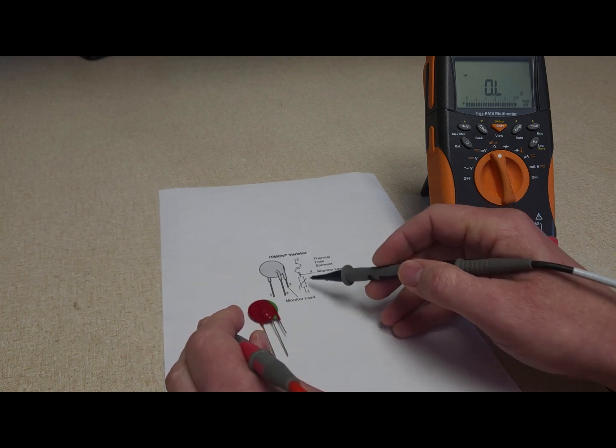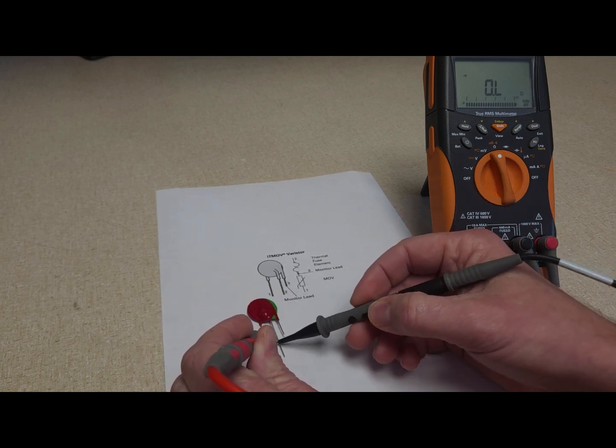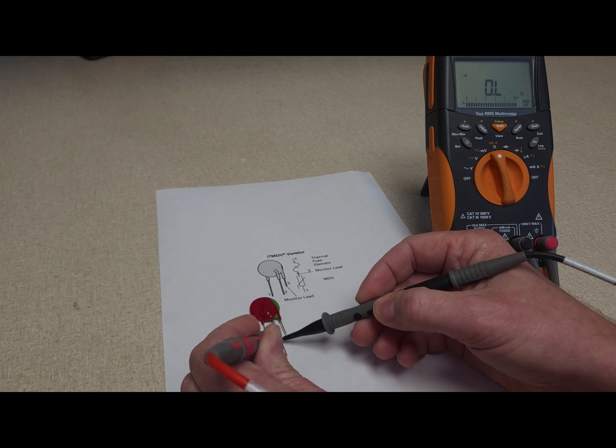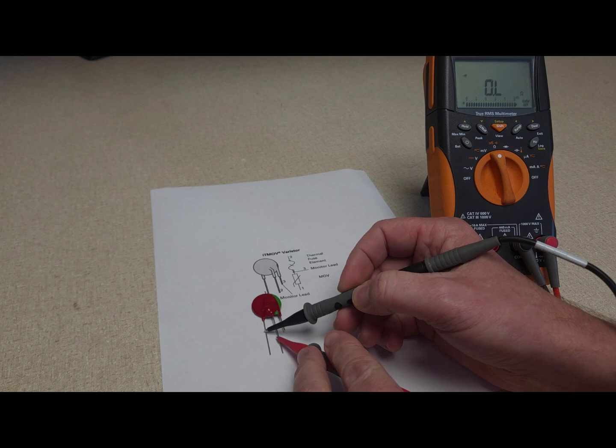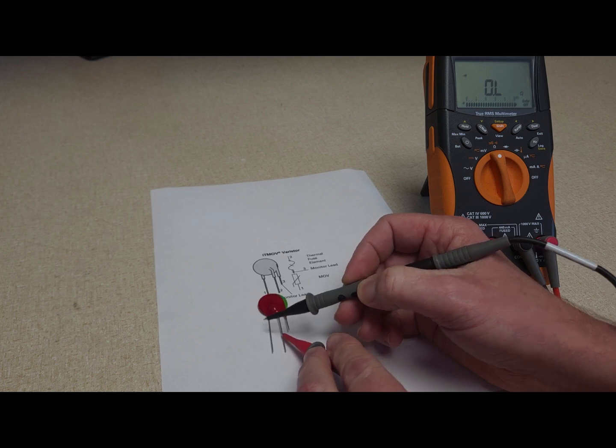To test across the MOV we'll go to legs one and two, right here and here, and I should expect nothing and sure enough I get nothing. Now I'm going to switch the leads as well to verify that I've got nothing in the diode function the other way.